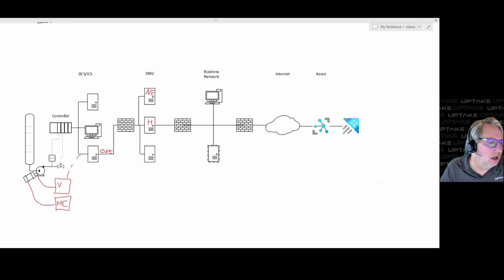So you might get a small, thin subset of the data transmitted to the control system so the operator can detect if something has gone badly wrong, or so the operator can start or stop the motor controllers. But a lot of the data in vibration systems and motor control systems, and even things like instrument diagnostics, tends to be stranded in the control system, or even stranded upstream of the control system.